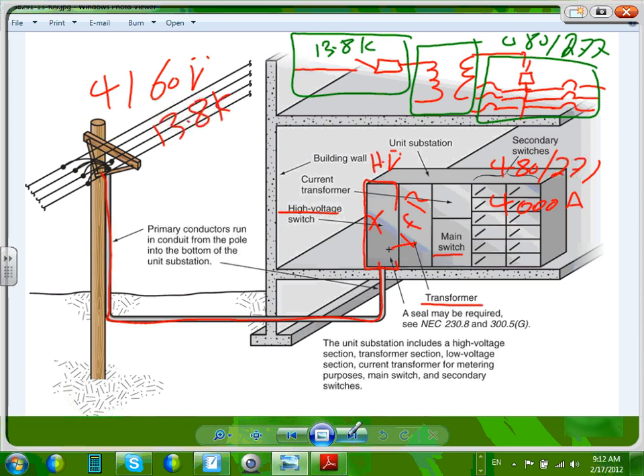They want you to pay, so their metering is happening right here. They call it hot metering. They meter right at the substation. They put their meter CTs and PTs right at the substation. Any question about this substation, underground feeder?